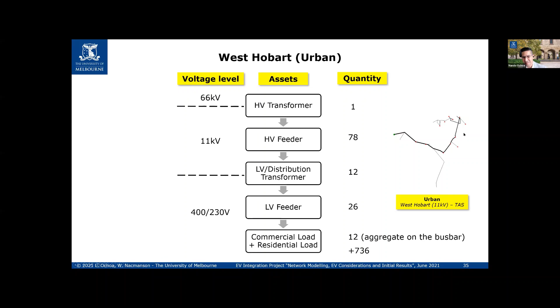So we have this model, and when we start running the power flows, just with level 1 charging, what you can see is that at 0% electric vehicle penetration, meaning nothing, the voltage limit is 0.94 per unit, which is 6% below 230 volts for single phase customers. It's far from that limit, because everything is perfectly fine. Normally we boost our distribution transformers to give an extra push of voltage, so everything is fine. In terms of the utilization of the assets, it's perfectly fine as well. The high voltage feeder utilization is perhaps a little high, but that's because it's a very heavy demand day.